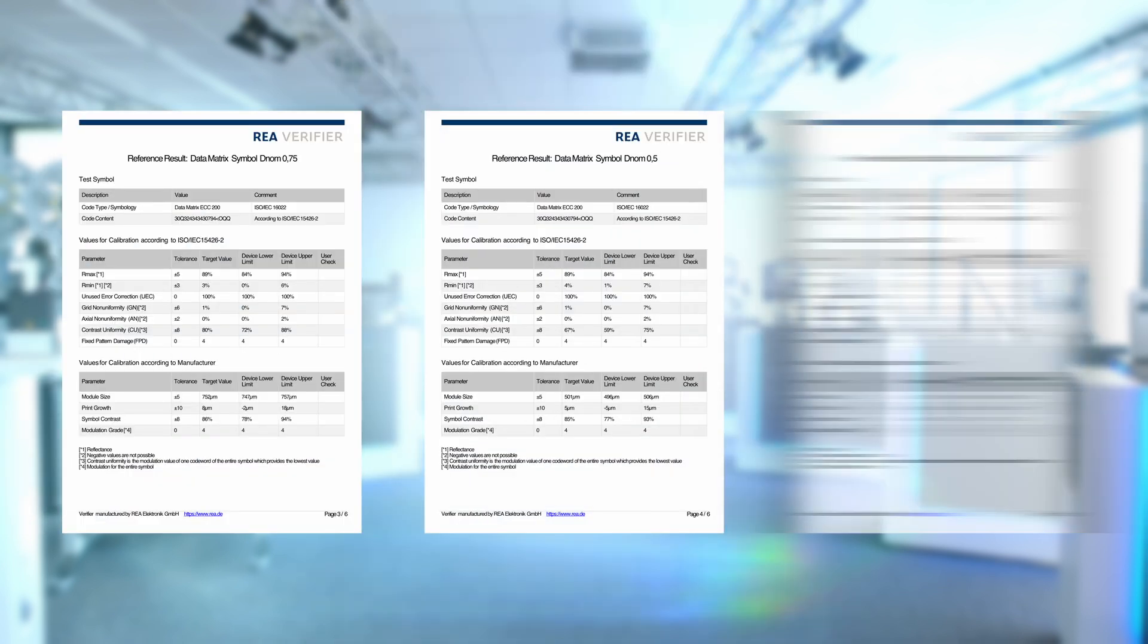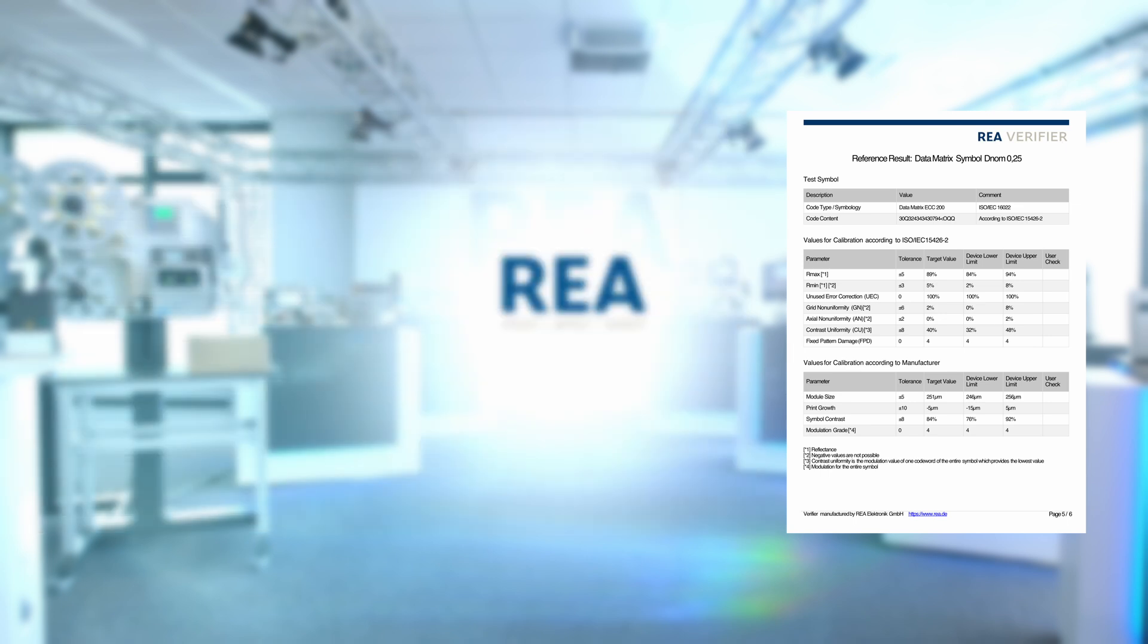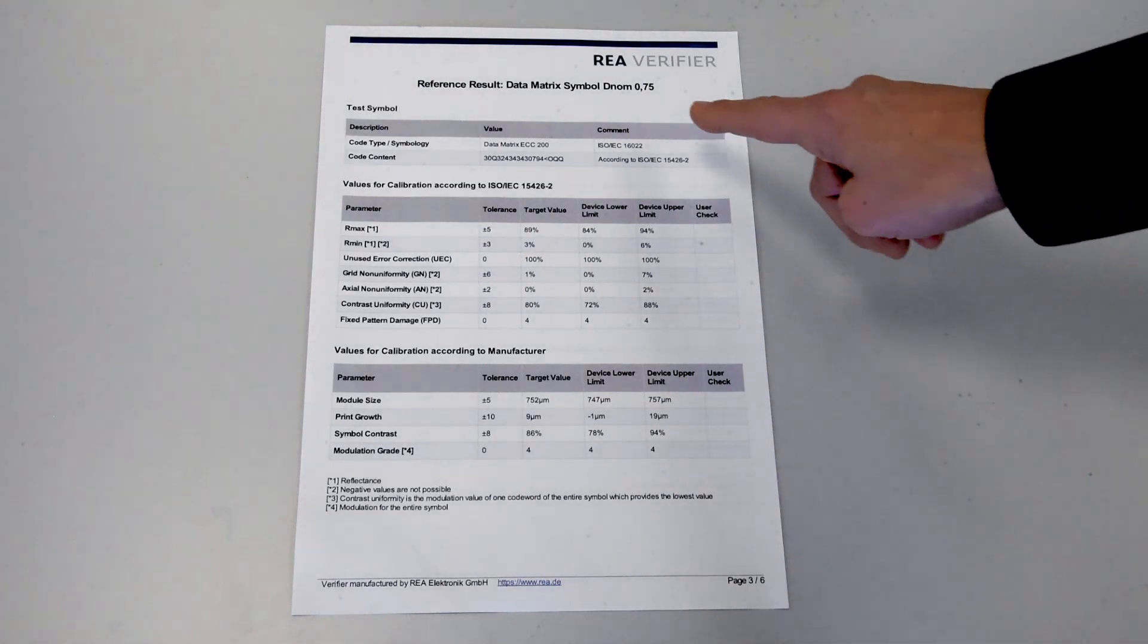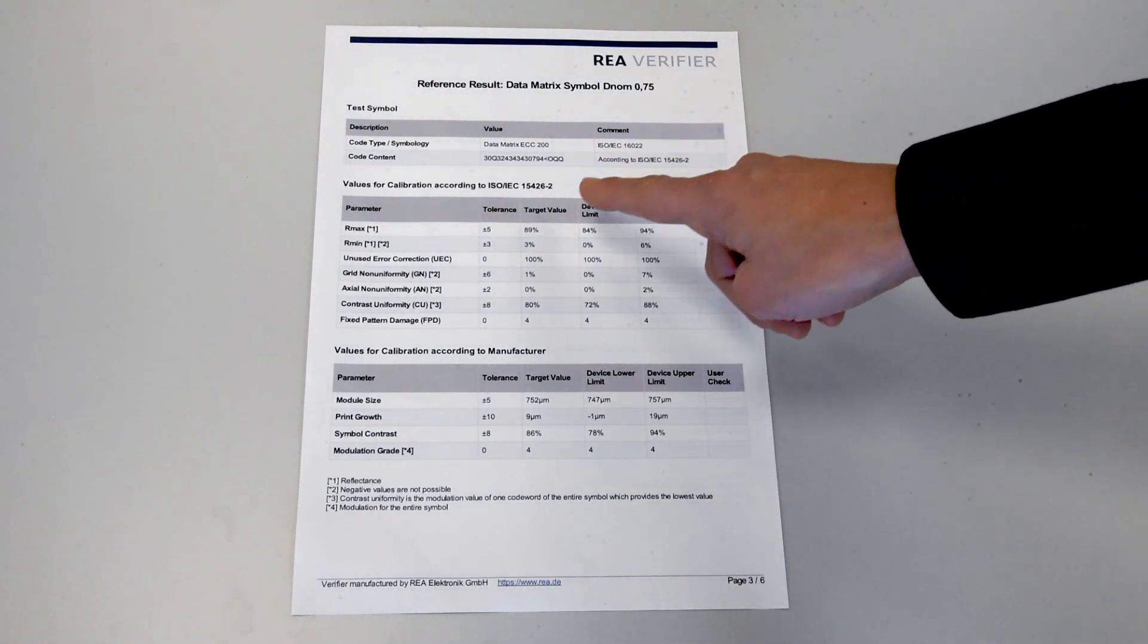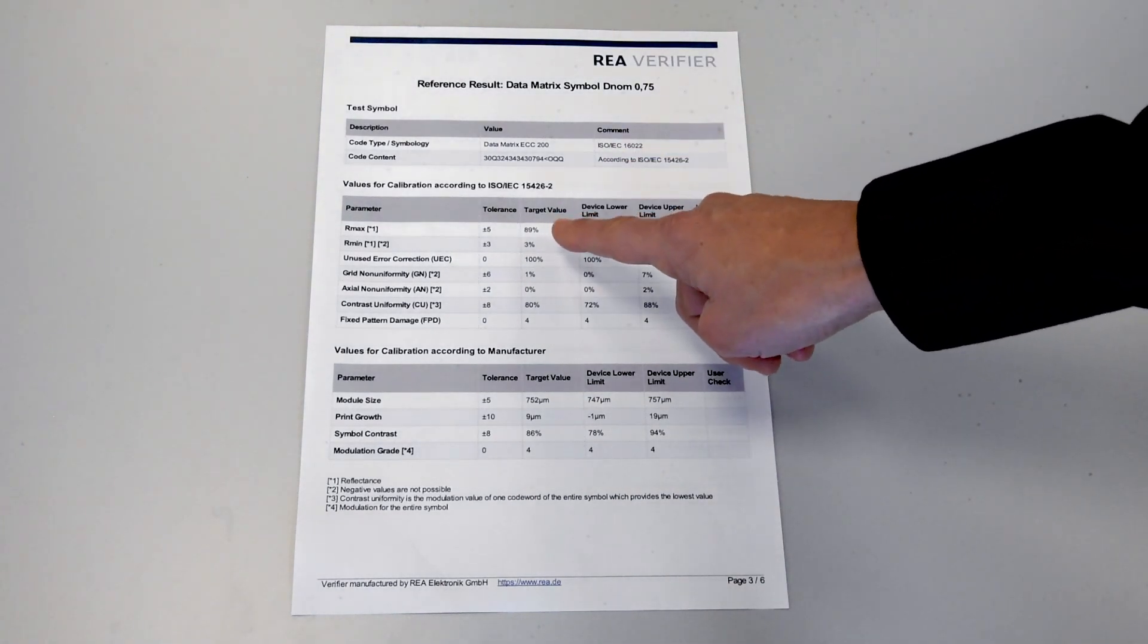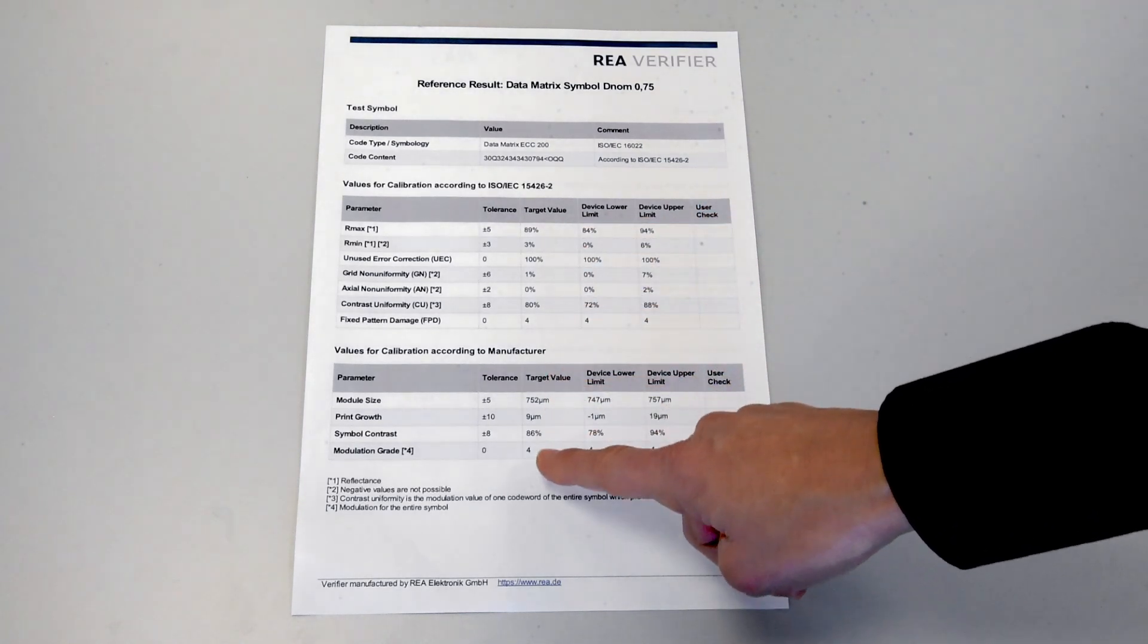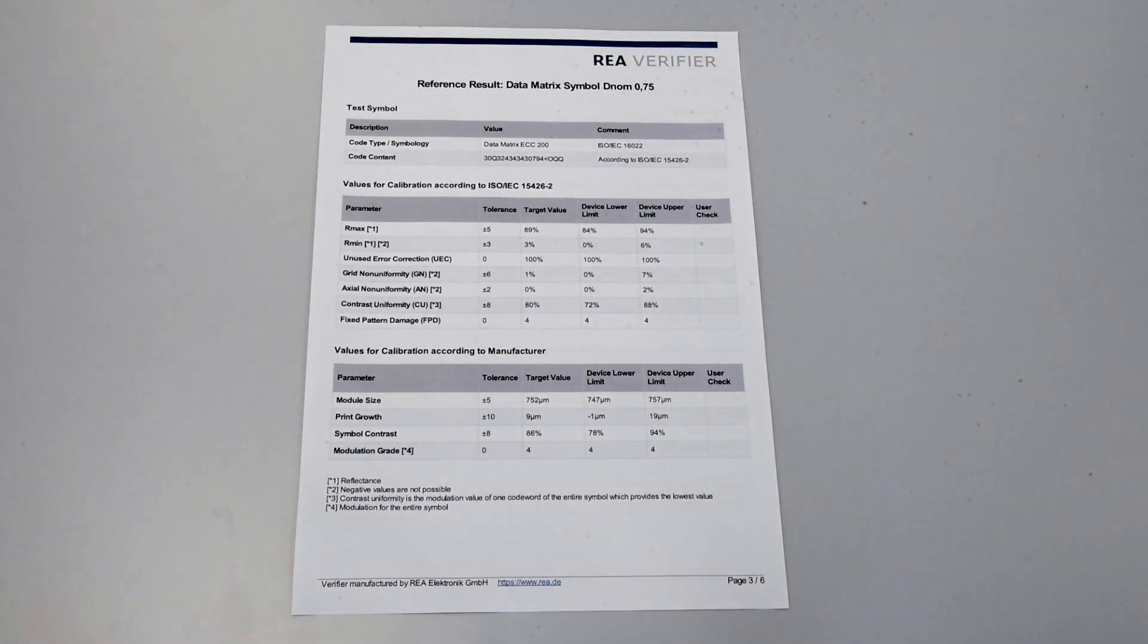On pages 3, 4 and 5 we will find the reference reports for the three different symbols on the calibration card. We look on page 3 with the reference results for module size DNOM 0.75 and write off the target values to the software in column DNOM 0.75.